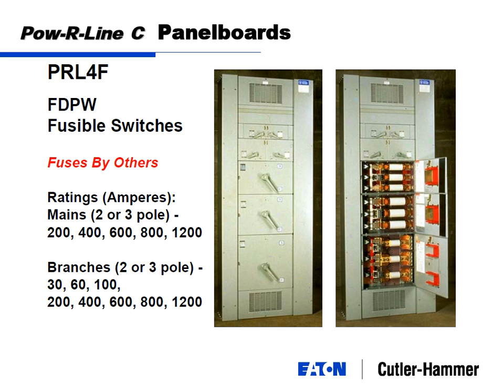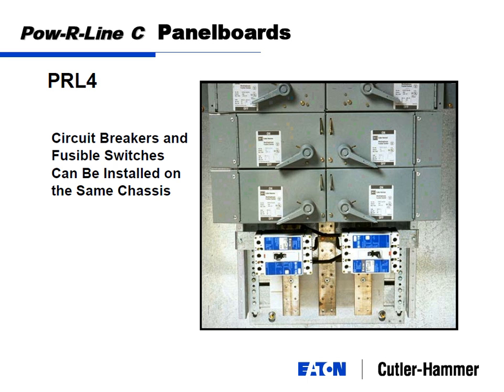The other way there's going to be differences is in footprint. If you look at these fuses, I'll say this one's a 200 and a 400 and a 600 stacked up there. And side by side, you can put 200 amp switches side by side. This is 200 amp switches. This is two 225 amp circuit breakers. And the bigger you get, this is the 400 amp circuit breaker, and the 400 amp switch was probably this high. So a lot of times people measure the cost with footprint.